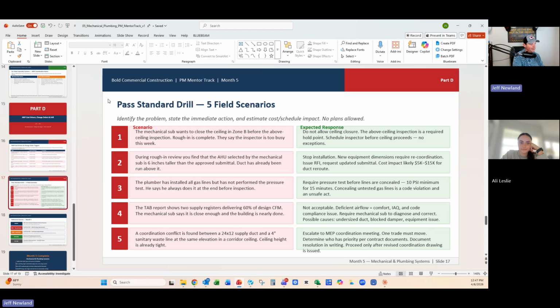So I would find out why we can't install the current unit. Number one, I would say, well, I approved a submittal that is not correct, and the design team did too, apparently. But you would have to research this to say either we need the right unit, like why was the right unit not submitted, or you need to start exploring options to raise the ductwork. Either way, it is what they call a hold point. So stop installation. New equipment dimensions require recoordination. Issue an RFI. Request an updated submittal. Cost impact likely 5 to 15K for duct reroute.